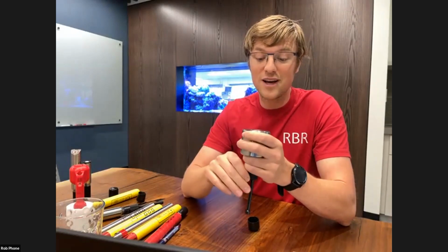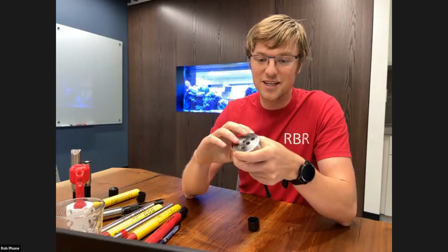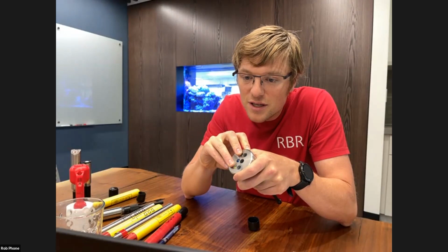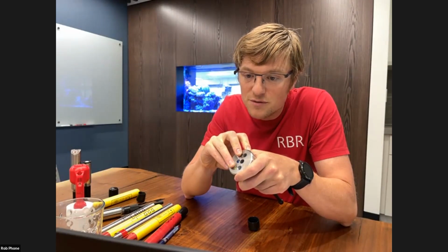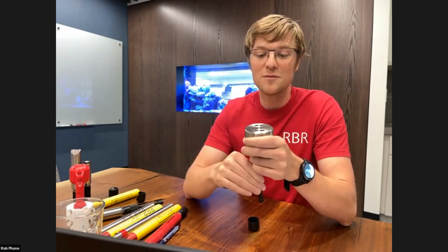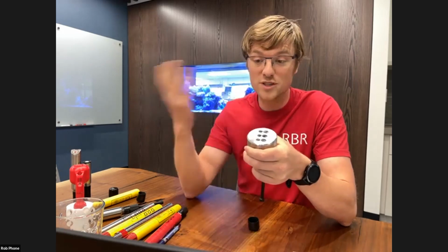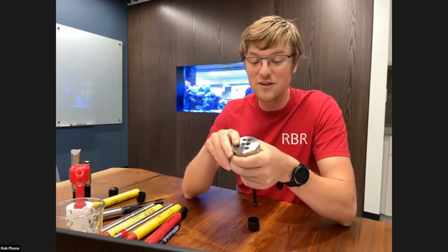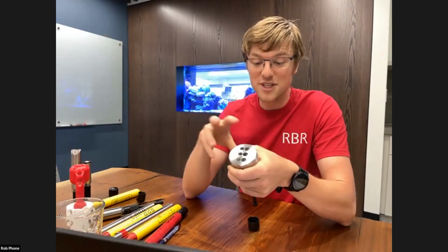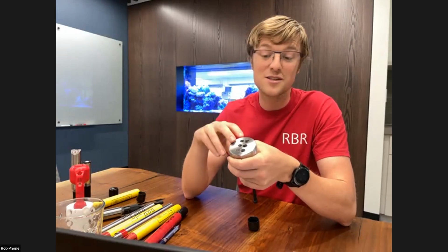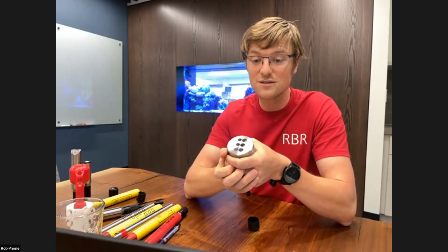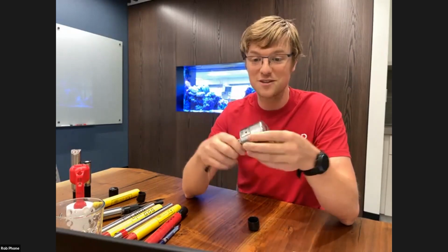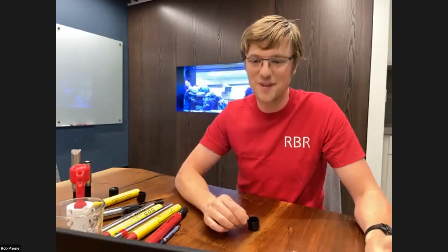So it's quite, I think it's ideal to have it in that construction. Another one for turbidity and backscatter, is turbidity the only output? Can the sensor be calibrated to produce volume scattering function? Yes, it can, certainly. That is something we'll work towards, to doing a proper volume scattering function. We've talked a lot with various scientists to ensure that we have the optics designed such that we can do a nice characterization of the volume scattering function and calibrate it accordingly. So that'll certainly be available in the near future.